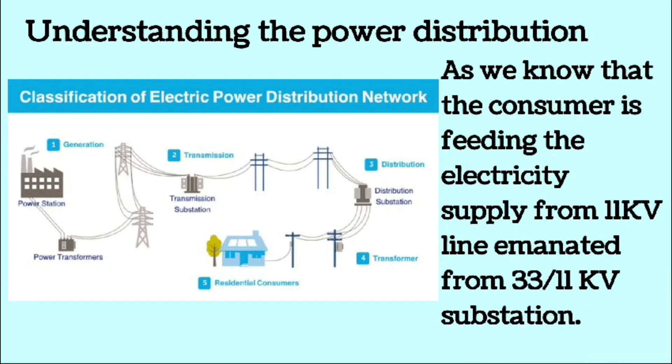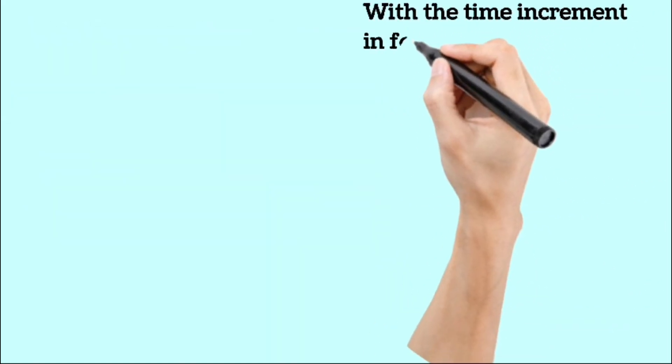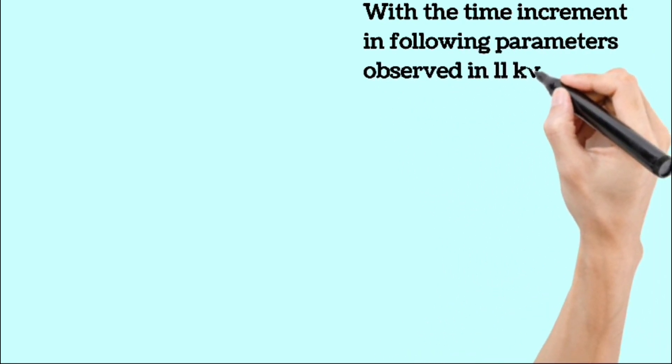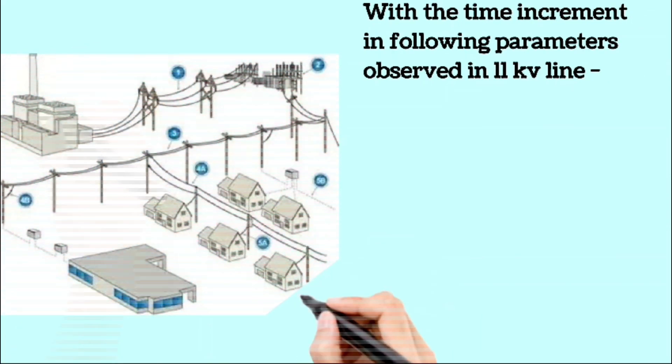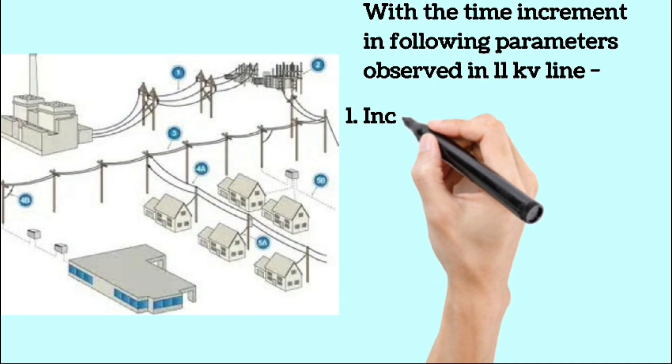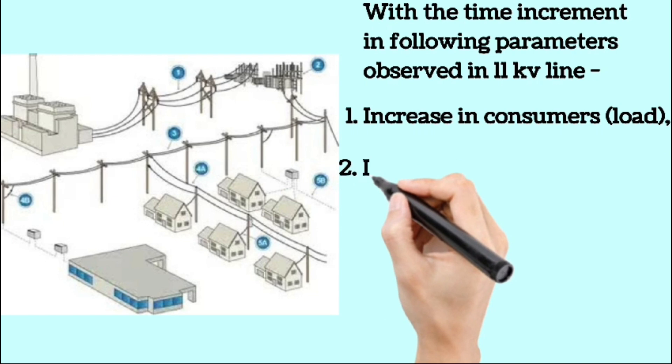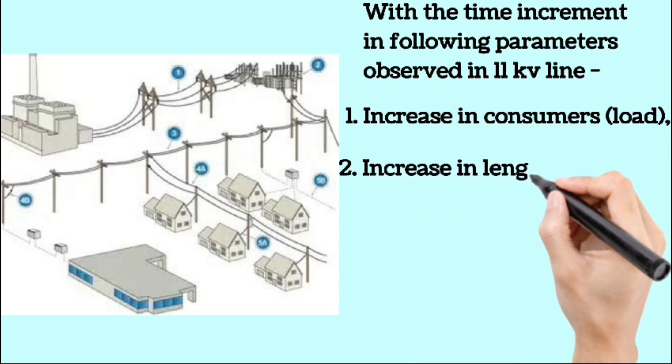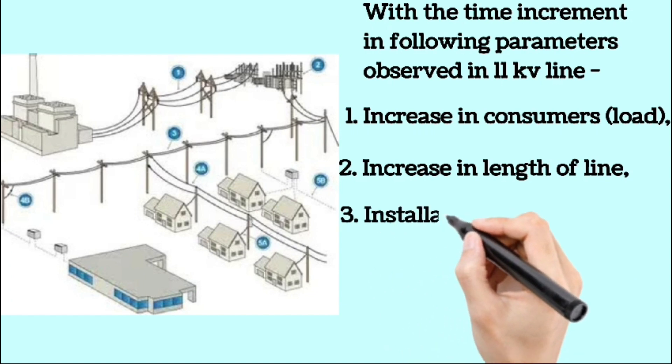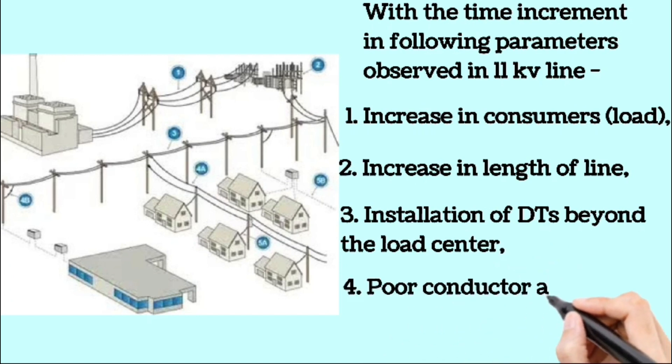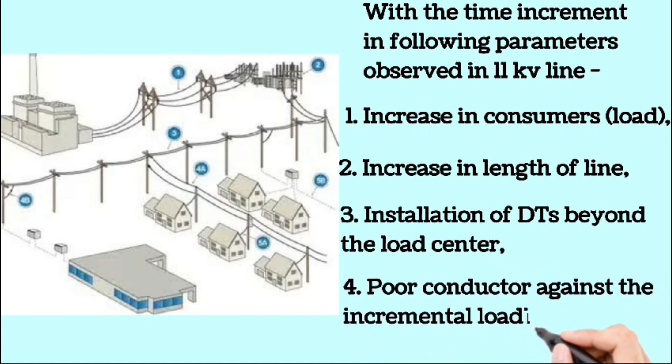Over time, the 11 KV line faced several issues leading to overloading and resulting in poor voltage regulation on the feeder. The primary factors contributing to poor voltage regulation include: a continuous increase in consumers which causes an increase in load, unplanned and unrestricted extension of the line, load unbalancing, failure to install additional distribution transformers at load center, and lack of conductor replacement despite these increasing demands. These factors collectively contribute to poor voltage regulation in any 11 KV feeder.